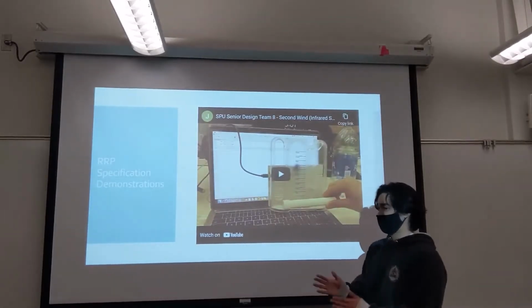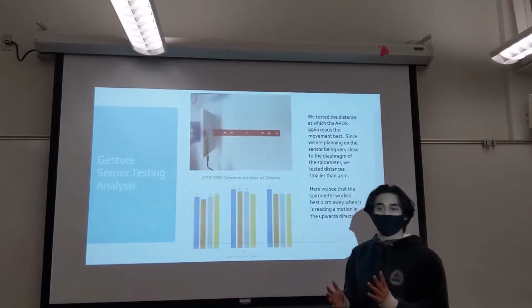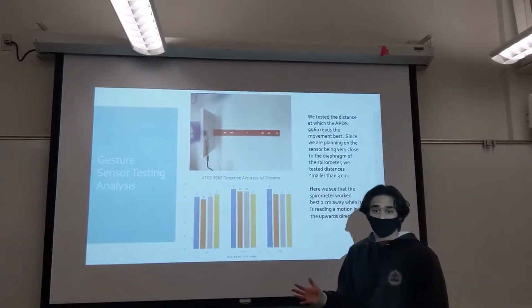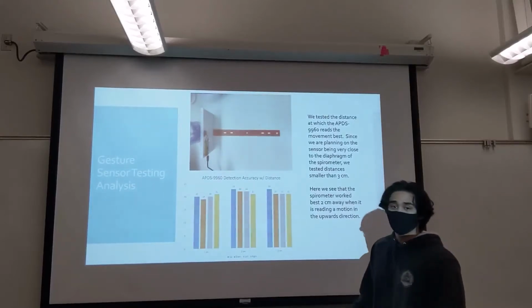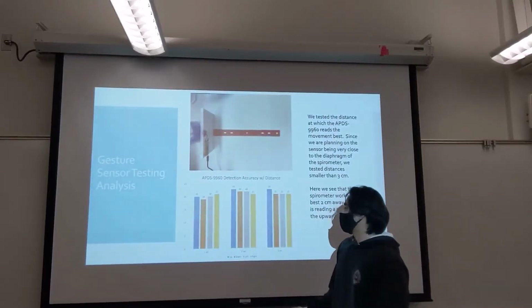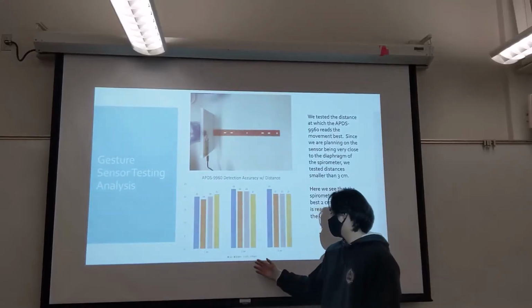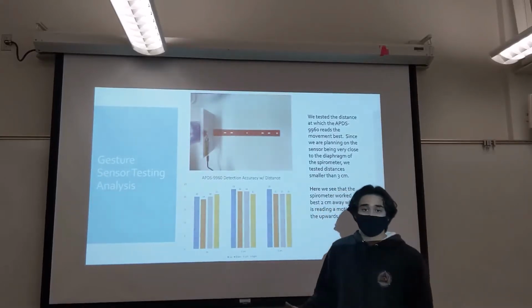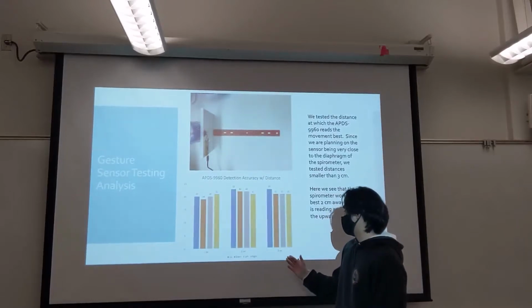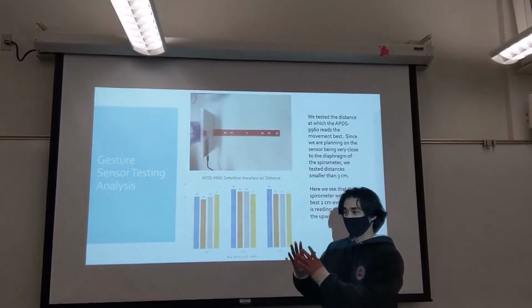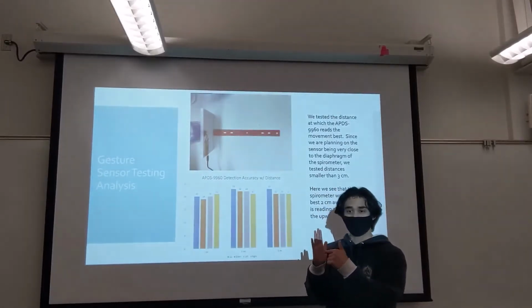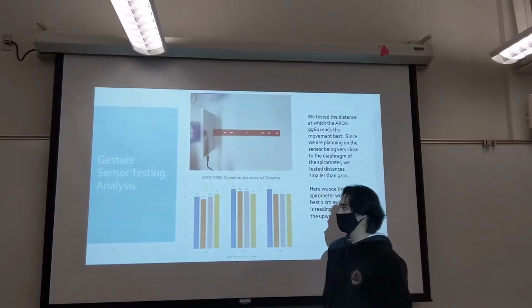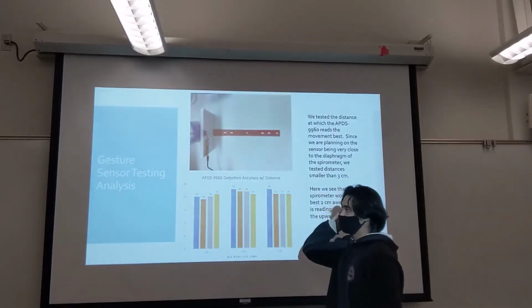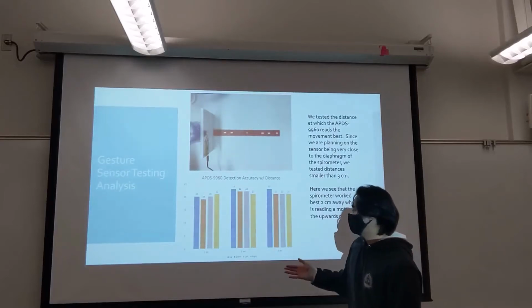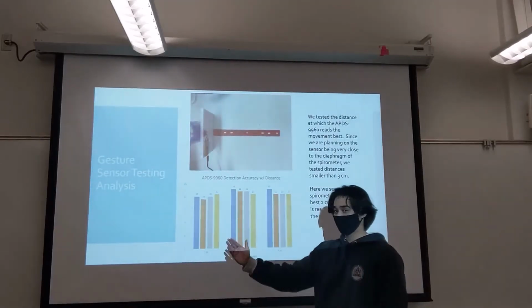One of our next plans for this sensor was to determine how far away from the housing the sensor needs to be to get the most accurate readings. To test this, I tested from 1 centimeter away, 2 centimeters away, and 3 centimeters away. The reason I didn't consider larger distances is that inside the electrical housing there's only so much space we can have the module stay away from the housing, and up to 3 centimeters is what we planned. I tested each direction of the sensor, up, down, left, and right, 25 times.